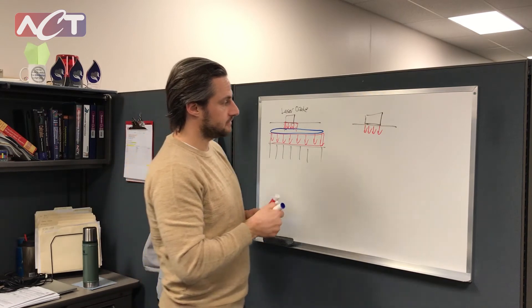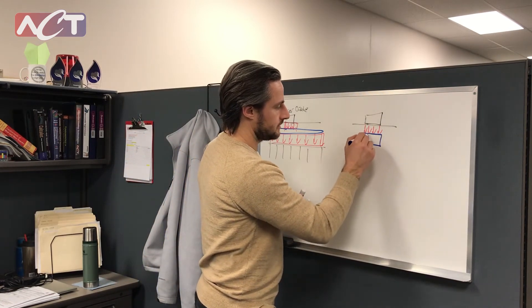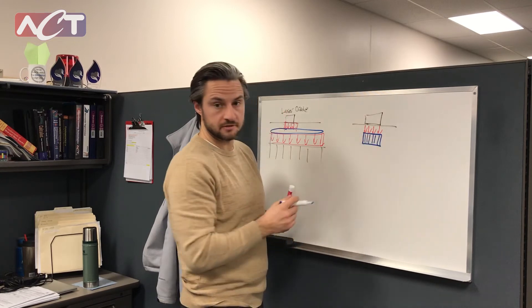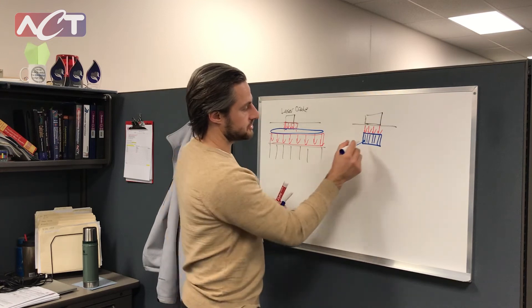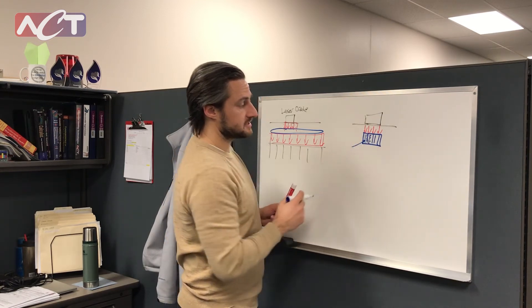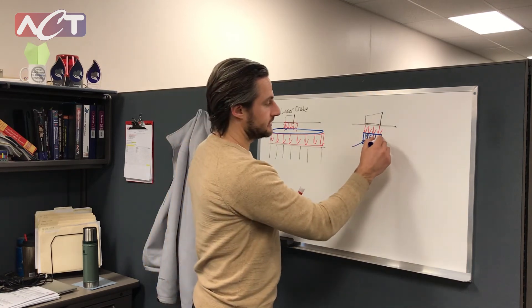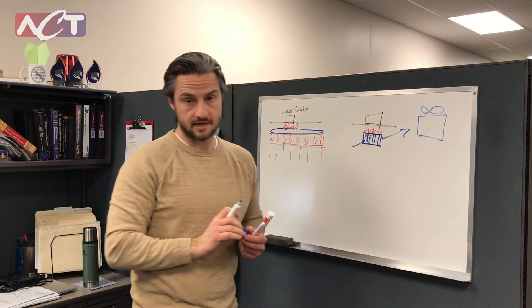In order to handle such a high heat load we may need a very exotic cooling solution like a liquid cooled solution using micro channels where we're pumping a fluid into the solution. We have a lot of surface area on the inside of our cold plate to dissipate that power and the liquid then travels on to some sort of heat exchanger where we can dissipate it to air.